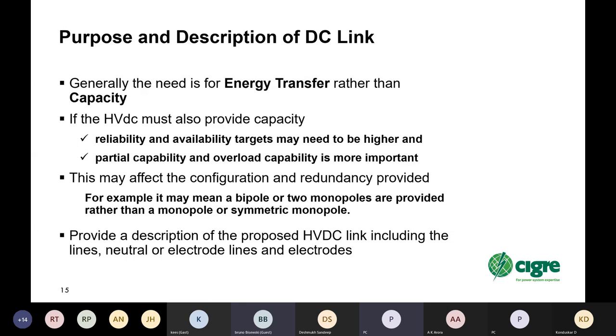If the DC system has to provide the equivalent of generator capacity, then the reliability and availability design targets may need to be higher. And things like partial capability and overload capability, especially when you lose a pole, are much more important. This could affect the configuration and the redundancy that you would specify. For instance, it may mean that you specify a bipole or two monopoles rather than a single monopole or symmetric monopole. And so the idea is to provide a description of the proposed HVDC link, including the lines, neutral or electrode lines, and the electrodes, if applicable.